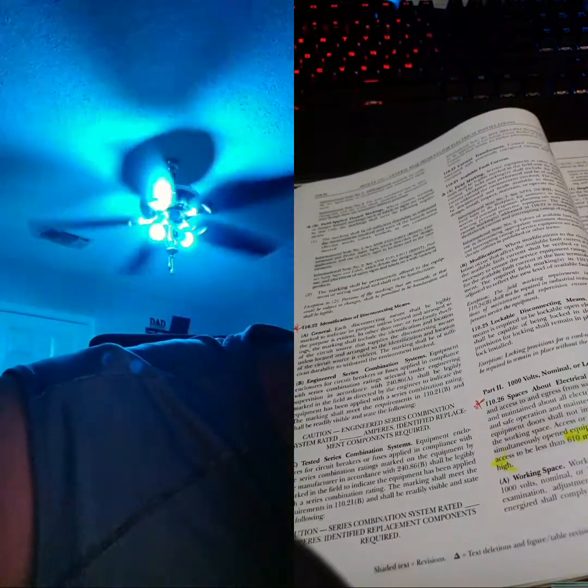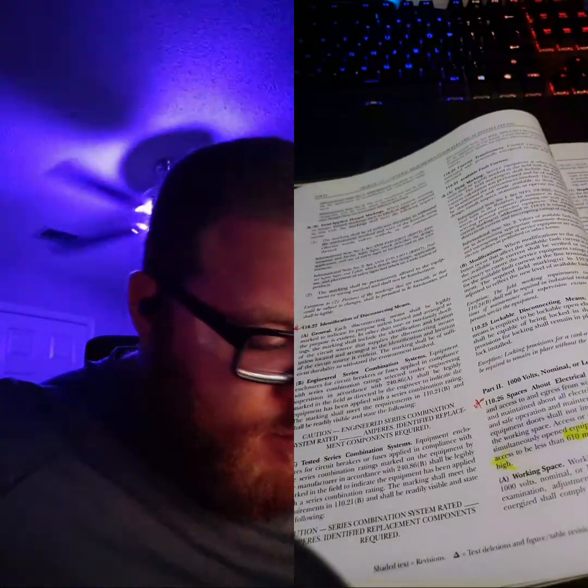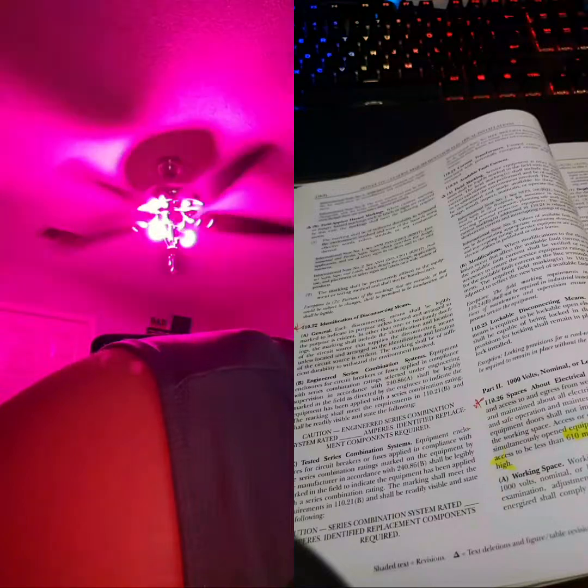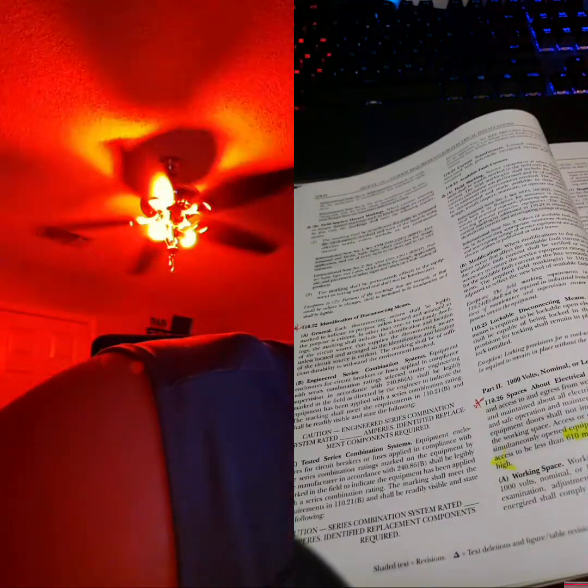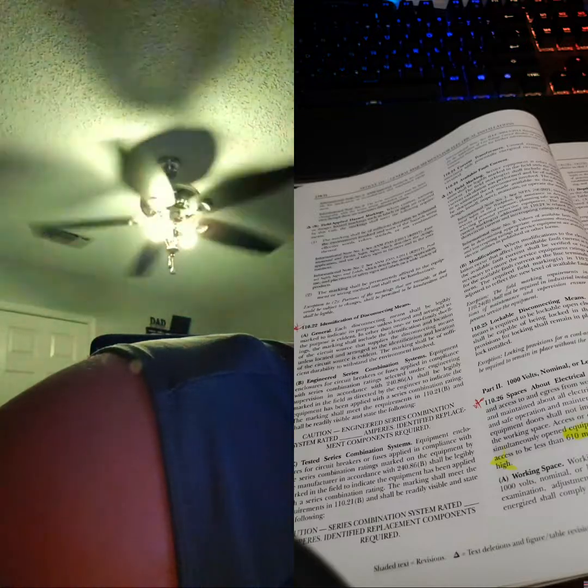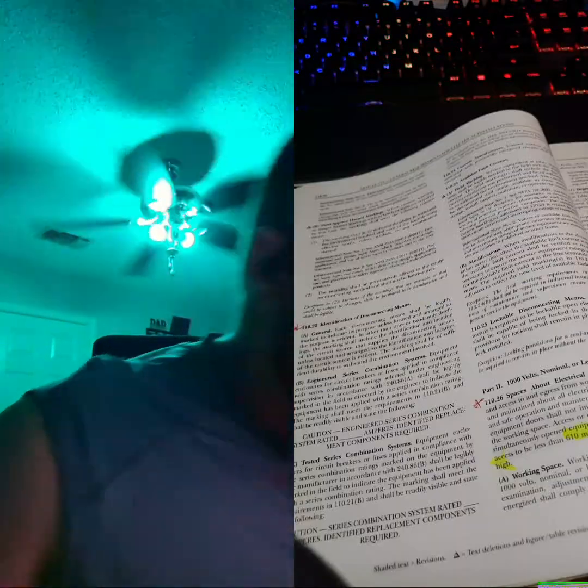Today I was looking at TC tray cable because this guy ran it to a mini split unit above a ceiling grid for some reason, and it looked like cord. I said, you can't have a cord above. He said it's not cord, it's tray cable. I said, shouldn't tray cable be in a cable tray? He said no. I asked why they would make tray cable if it's not for a cable tray? And then it turns out it has to be in a raceway or in a cable tray.